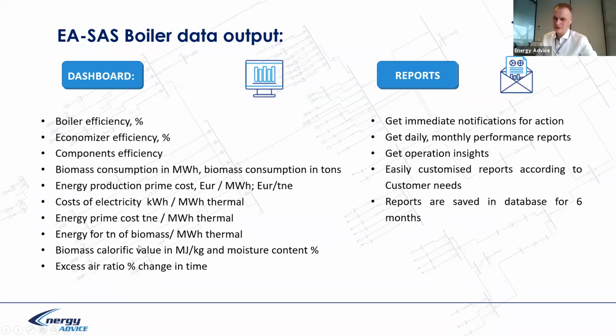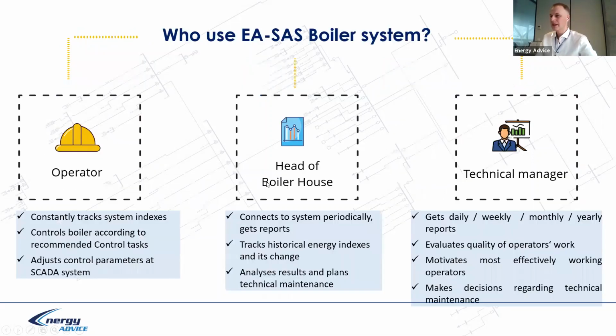So all calculations are done each 5 minutes. Later, this data is processed to 1 hour data, or 1 day, 1 week, 1 month data, according to your needs. And you get reports and immediate notifications, like a general instrument for a cloud solution. And who is a user of the boiler system? If you have an operator, of course, the operator constantly reviews the existing situation. If you have a head of a boiler house, he of course gets reports and reviews data, analyzes maintenance indexes, KPIs. And if you are a technical manager, you of course have your own role. So you motivate effectively working operators, you make decisions on maintenance, and also fuel supply issues, fuel quality issues, everything related to the boiler.